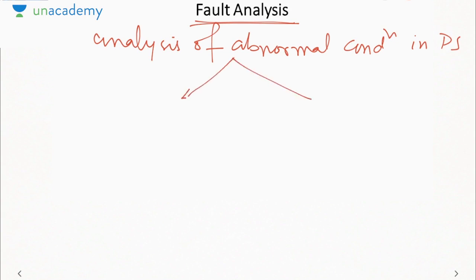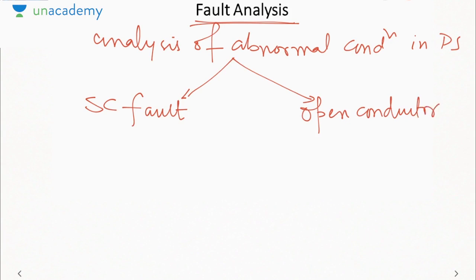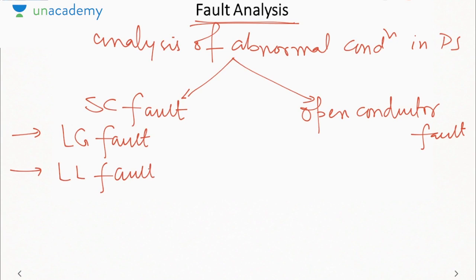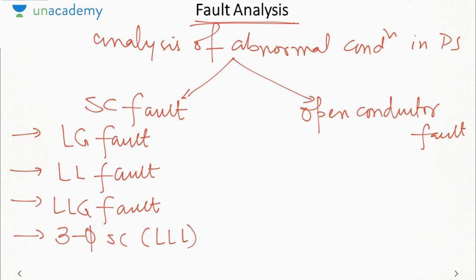Now fault analysis is divided into two parts. Short circuit fault, whenever there is a short circuit it is an abnormal condition, or open conductor fault, whenever any conductor gets open circuited. Now in case of short circuit fault we have the following categories. First is your line to ground fault, that is one line is connected to ground. Out of three lines, one will be connected to ground. Other is line to line fault, that is two lines are short circuited together. Then next is LLG fault, that is two lines are short circuited as well as they are connected to ground. Then three phase short circuit, that is LLL fault, and last will be triple LG fault, that is all the three phases are short circuited as well as they are connected to ground.